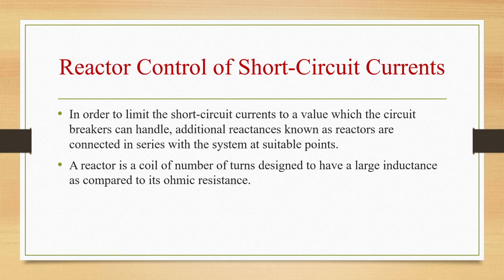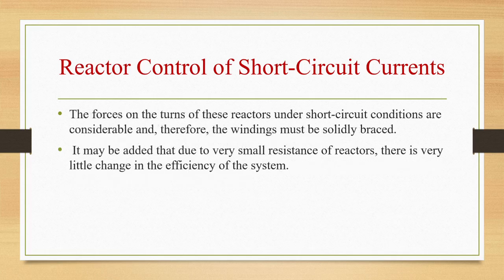A reactor is a coil of a number of turns designed to have a large inductance as compared to its ohmic resistance. The forces on the turns of these reactors under short circuit conditions are considerable, and therefore the windings must be solidly braced. It may be added that due to the very small resistance of reactors, there is very little change in the efficiency of the system.